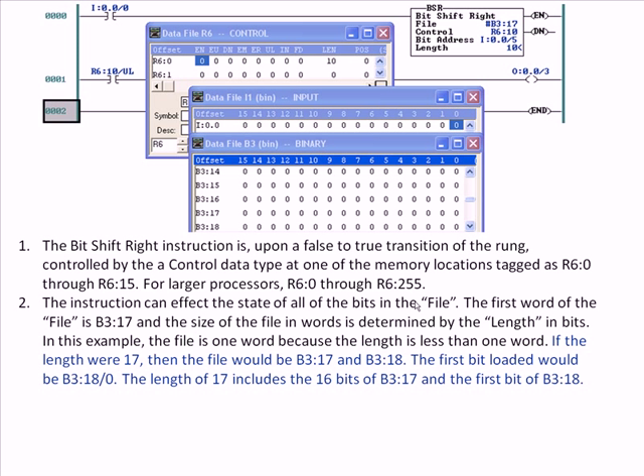Just like the Bit Shift Left, if the length were 17, the file would be B3:17 and B3:18. The first bit loaded would be B3:18 bit 0 — and that should be your first clue of what's different with the Bit Shift Right. With the Bit Shift Left starting at B3:17, you would have loaded in B3:17 bit 0. But with the Bit Shift Right with a length of 17, you're loading what would normally have been the last position and going backwards — to the right instead of to the left. The length of 17 includes the 16 bits of B3:17 and the first bit of B3:18. The file structure is the same for both BSL and BSR — you're just shifting in a different direction and loading from the other end.